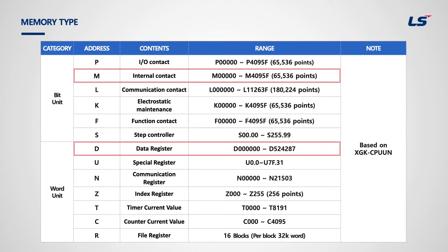Users mostly use M memory and D memory for internal memory. The difference between the two is that the last digit in M memory is a bit because M is a bit-based memory, whereas the last digit in D memory is a word because D is a word-based memory.